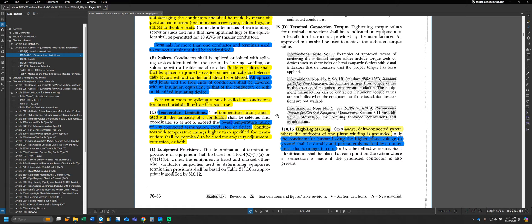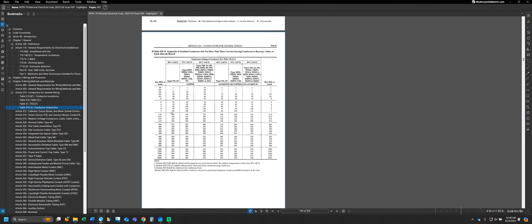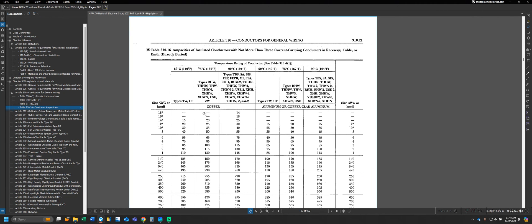I want to talk about that first part in more detail before we go on. Any conductor the NEC talks about is going to have a given temperature rating based on its insulation rating. I'll move us to Table 310.16 for conductor ampacities. Looking at 310.16 on a high level, we have three columns that repeat: 60 degrees Celsius, 75 degrees Celsius, and 90 degrees Celsius. Within each column, we have different types of conductors.